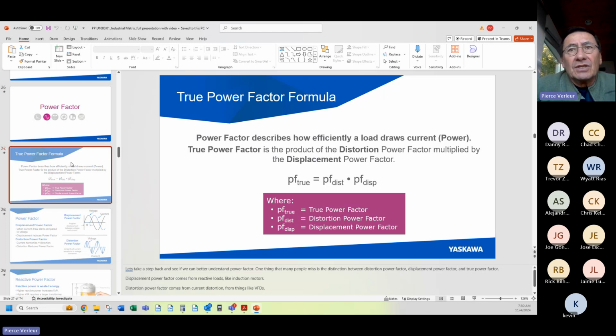Now, if you use the fluid analogy, if I pump 100 horsepower into a 10-inch pipe, and that pipe is nice and clean and smooth on the inside, and there's nothing in the way, most of that water is going to flow very nicely down to the delivery point. And you will get some waste energy in the friction of the water on the inside diameter of the pipe. And you can calculate that using your Hazen-Williams calculations, and that will come out to maybe 2-3% of energy that's wasted because of the friction of the water on the inside diameter of the pipe. And the power factor in that particular case would be about 0.97.